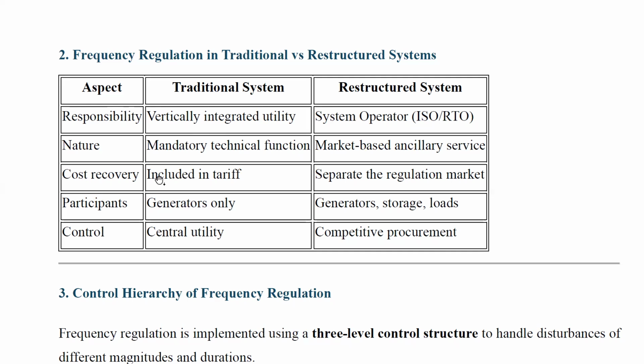Next come the participants. In the traditional system, only generators take part in frequency regulation. But in the restructured power system, generators, storage units, and loads are all involved. As for control, in the traditional system a central utility, say a grid system, will maintain it. But in the restructured power system, competitive procurement decides this. Which retailers, generators, or transmission companies maintain the frequency regulation constant will be preferred more in the market.